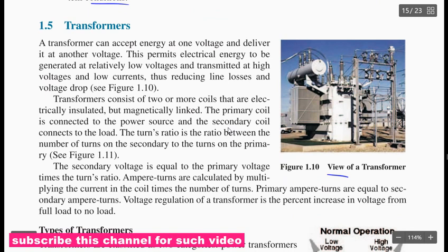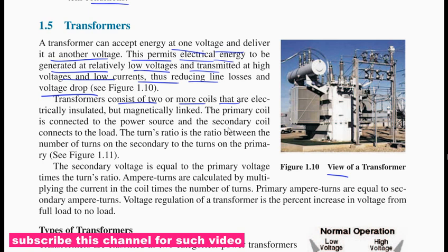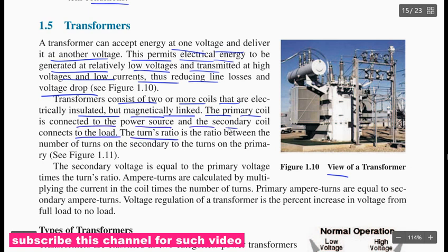The transformer can accept energy at one voltage and deliver it at another voltage. These permit electrical energy to be generated at relatively low voltage and transmitted at high voltage and low current, thus reducing the line losses and voltage drop. A transformer contains two or more coils that are electrically insulated but magnetically linked. The primary coil is connected to the power source and the secondary coil is connected to the load. The turn ratio is the ratio between the number of turns of secondary to the turns of primary, and the secondary voltage is equal to the primary voltage times the turn ratio.